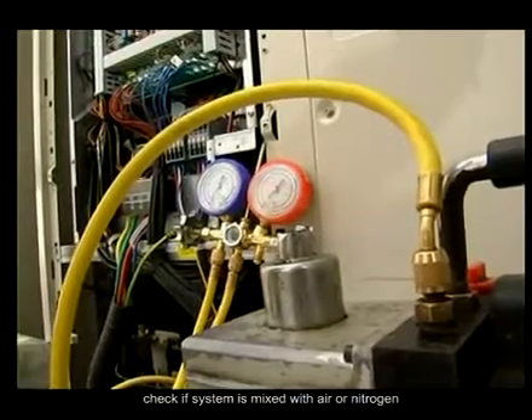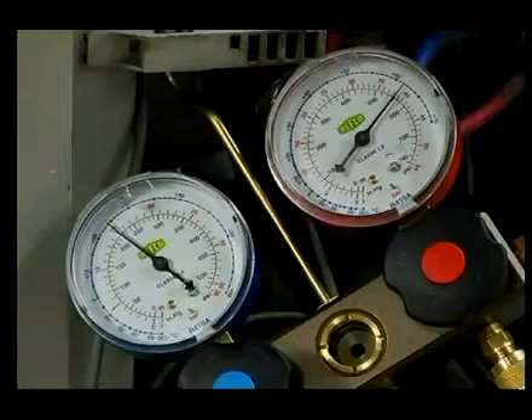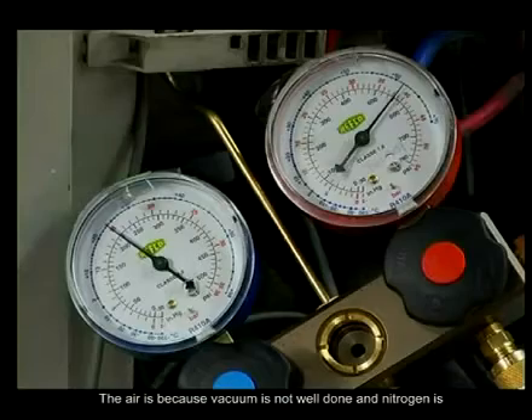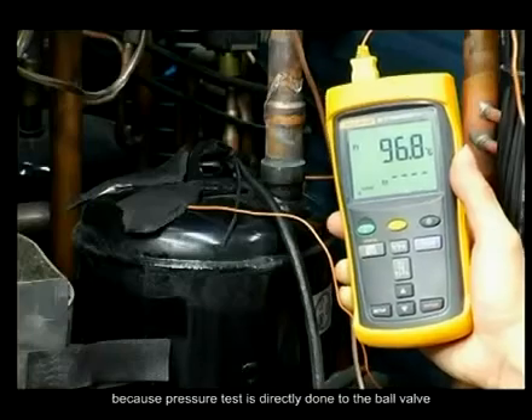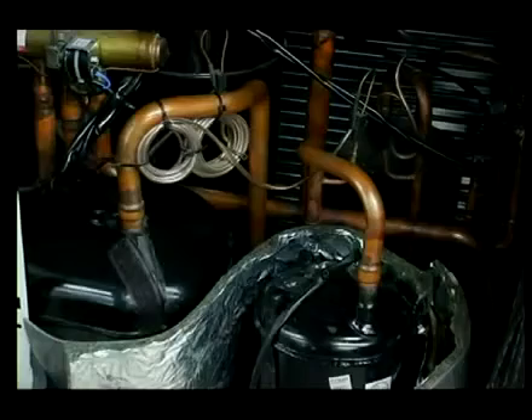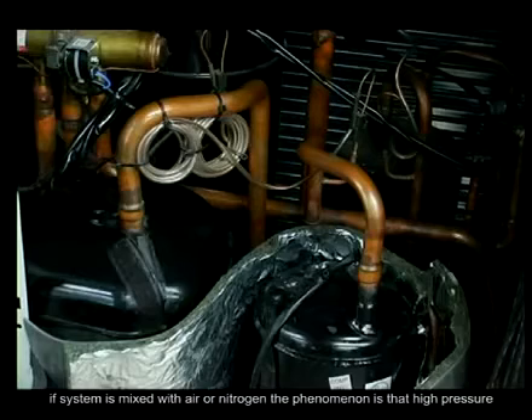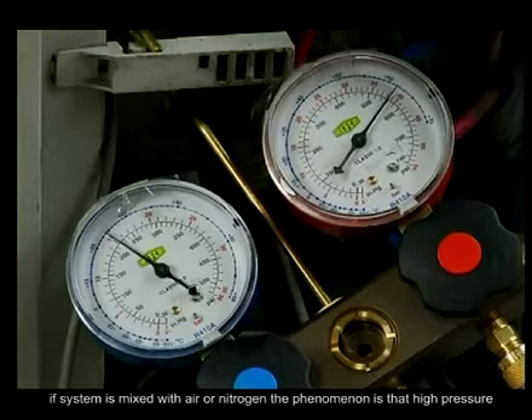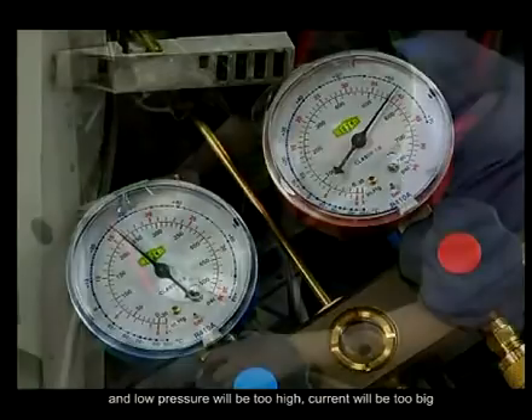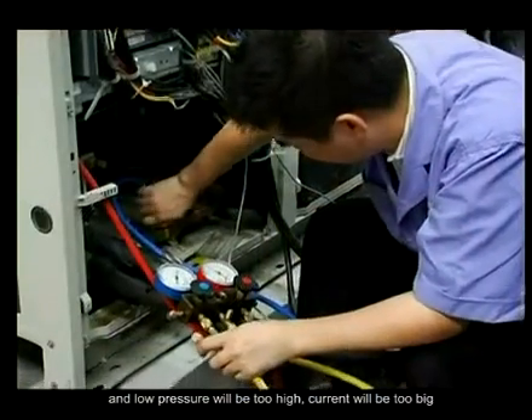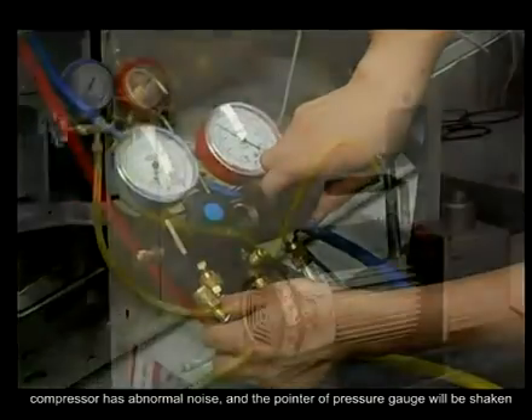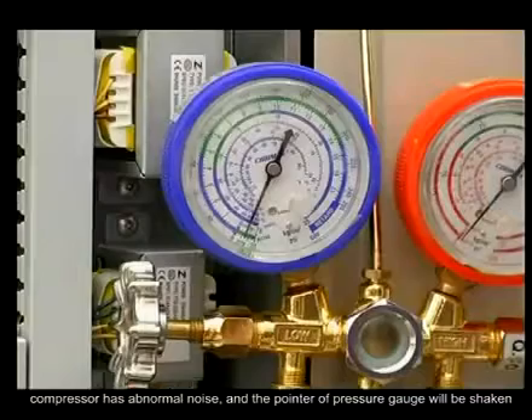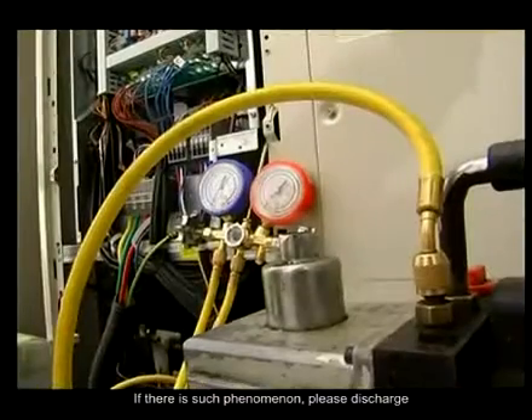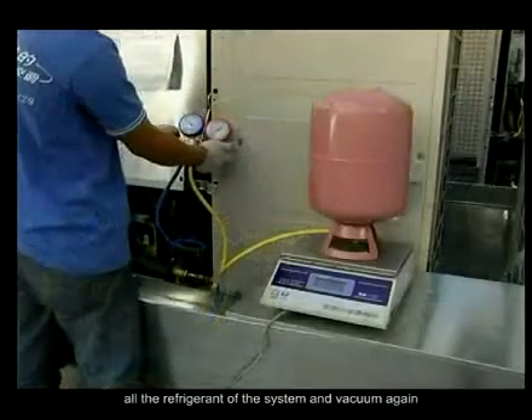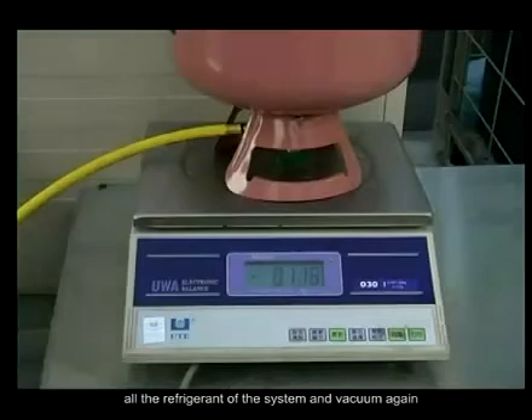Check if the system is mixed with air or nitrogen. The air is because the vacuum is not well done, and nitrogen is because the pressure test is directly done to the ball valve. If the system is mixed with air or nitrogen, the phenomenon is that high pressure and low pressure will be too high. Current will be too big, the compressor has abnormal noise, and the pointer of the pressure gauge will be shaken. If there is such a phenomenon, please discharge all the refrigerant of the system and vacuum again.